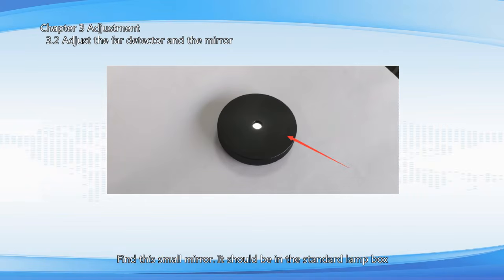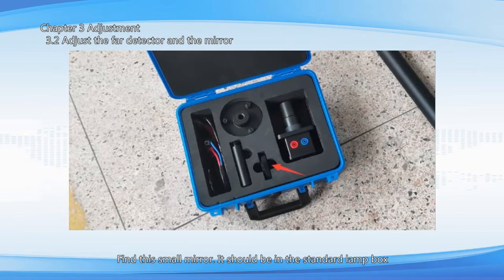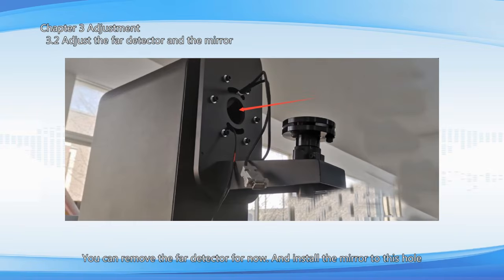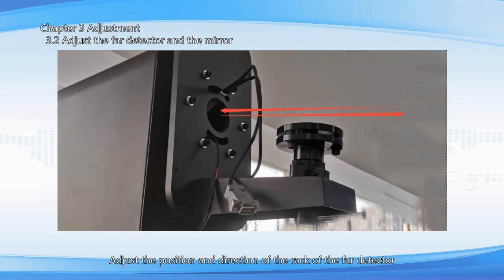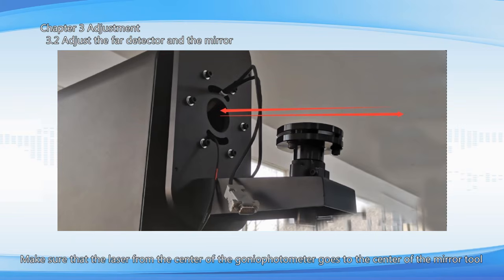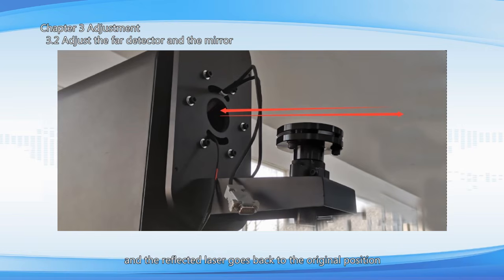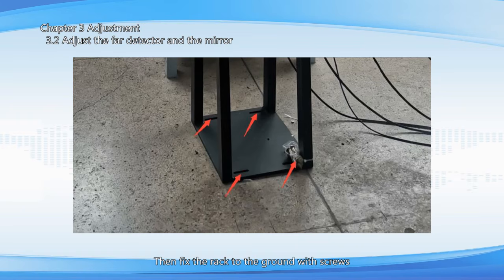Find this small mirror. It should be in the standard lamp box. You can remove the FAR detector for now, and install the mirror to this hole. Adjust the position and direction of the rack of the FAR detector. Make sure that the laser from the center of the gonio-photometer goes to the center of the mirror tool, and the reflected laser goes back to the original position. Then fix the rack to the ground with screws.